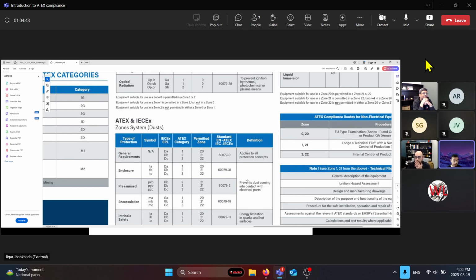Yeah, I'd made a note saying I was going to take this up to one of the senior engineers to get some feedback, because usually when we run into such a situation, I myself have only come across the intrinsically safe part, where the product has an intrinsically safe output for a certain part of the system to operate in a zone 0 or zone 1 environment, but the rest of the system is in zone 2. So that's a good point. I've noted it down, and I'll take that back to Marion and discuss it with him. Allow me a few days, and I'll get back to you next week on that. Great, thank you.